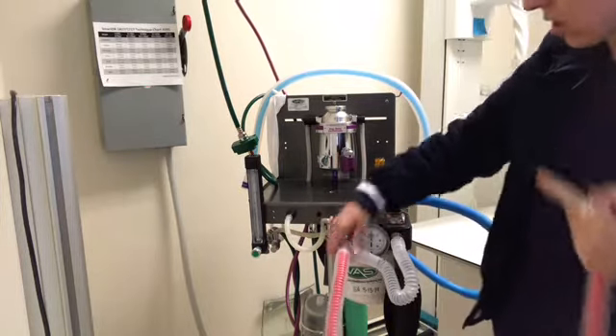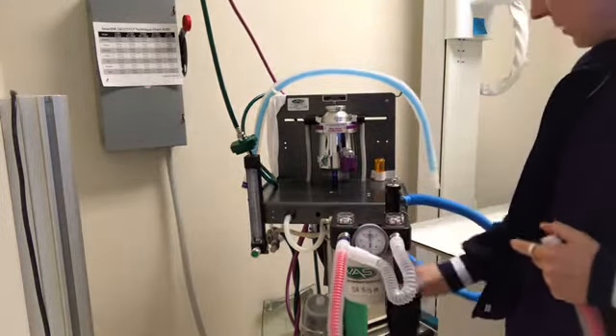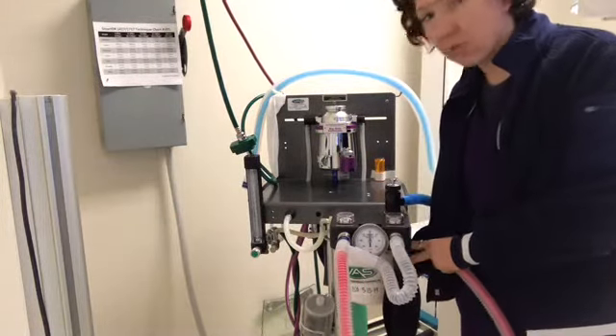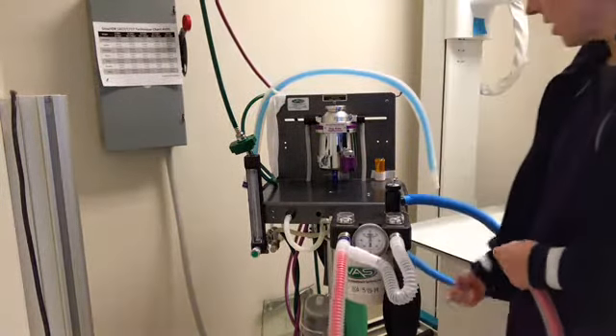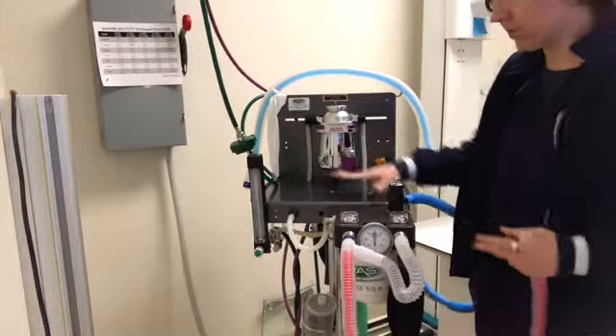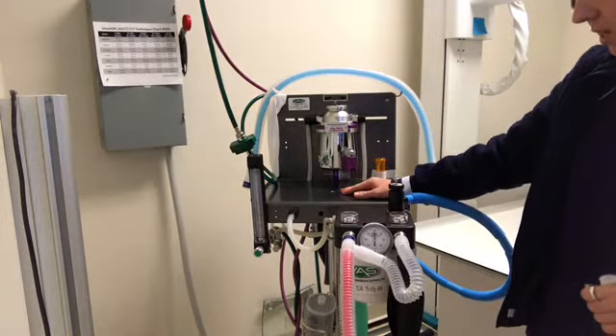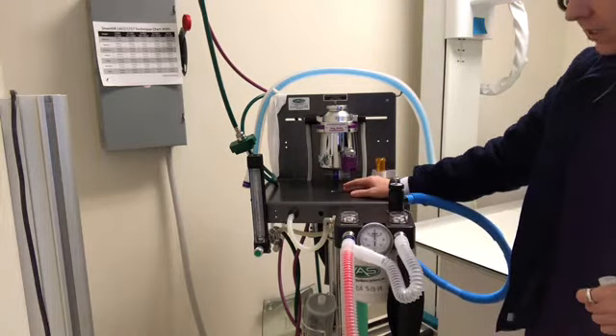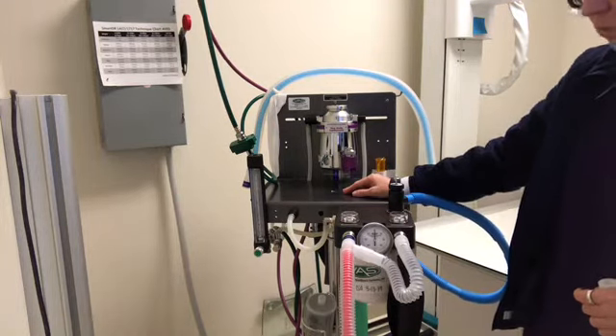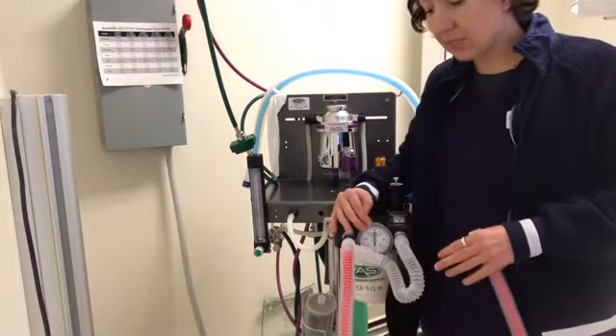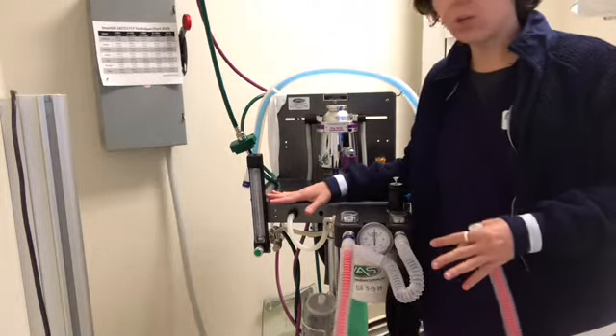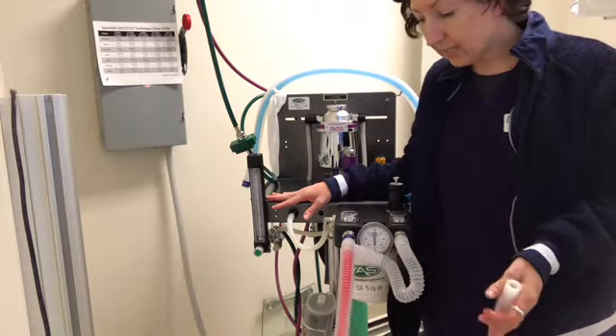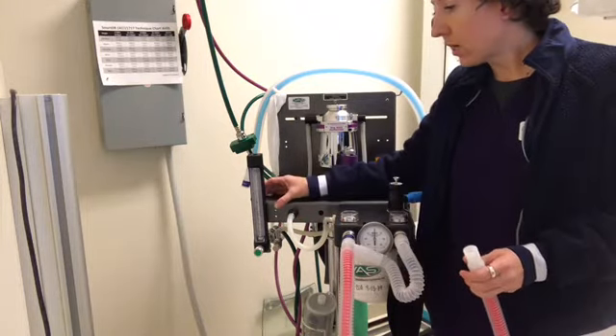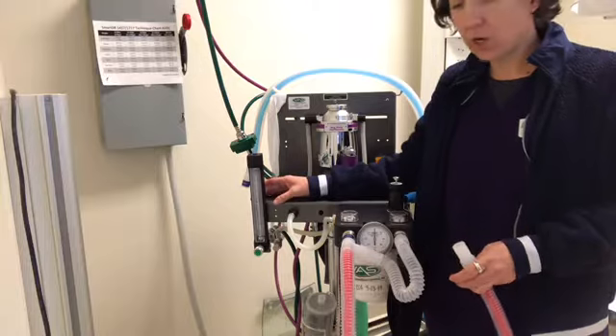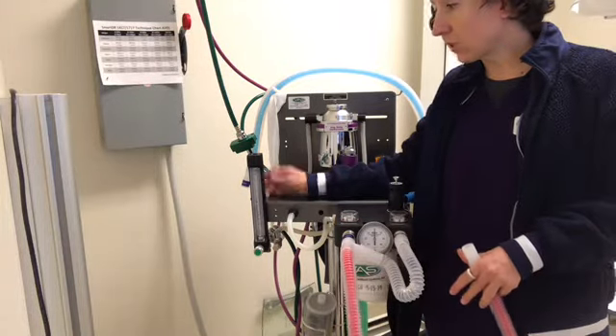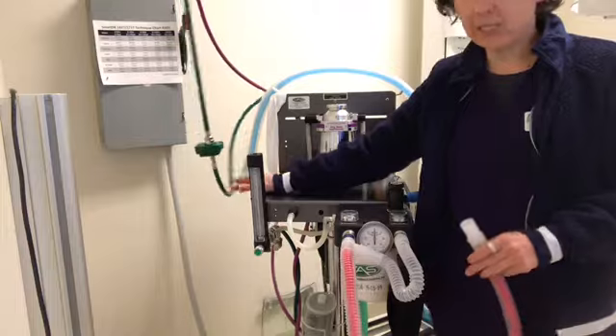So I would need to check all of my tubing, reservoir bag. I'd need to check the seal on the soda lime canister, and go through all of the machine parts to look for the leak. But if it does not drop more than 1 centimeter per second, then that means that the system is in good working order. And this is very important. You need to do this before every procedure to make sure that the system is running optimally.